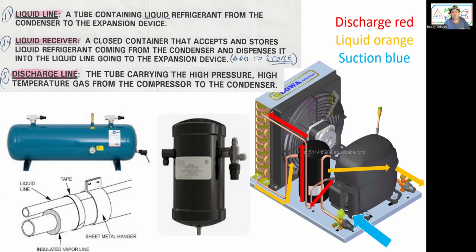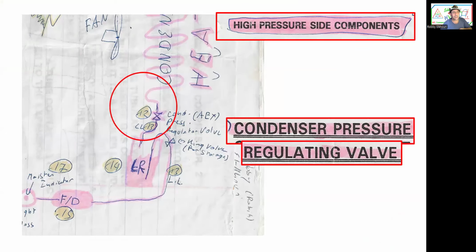Okay, anyway, this picture is a good one here. It shows the suction line in light blue, suction in from the evaporator. It goes to the compressor on top. The whole body of the compressor is vapor and a little bit discharged inside. And then the liquid discharge, red, goes down and up. It goes down and up like this because of vibration, so it doesn't break. It's like a vibration eliminator kind of. Goes to the condenser, vapor on top. Condenses first, de-superheat, condense, goes liquid. That's why it's called liquid receiver. Receives the liquid, goes out behind the compressor, liquid out to the metering device, to the evaporator, back, circles and circles we go. All right, next.